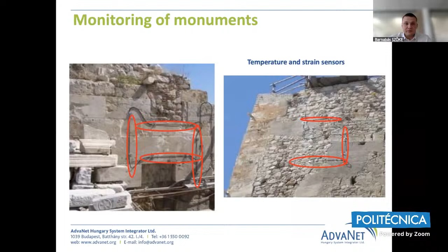What are the benefits of the fiber optic monitoring system compared to classical electrical sensors? It does not need a power supply at the sensor site, and it can cover up to 50 kilometers and 100 sensors per channel. We can expand the system easily, because we can connect sensors in series, whereas in the conventional case the sensors have complex cabling and difficult multiplexing techniques, so it's difficult to expand the system.